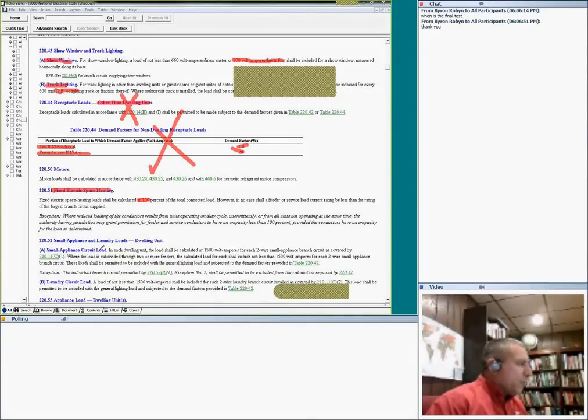And the laundry, small appliances. Can you guys see the small appliance circuit? Dwelling, you need 1500 volt-amps for at least 2 circuits. Laundry circuit, can you see where the laundry circuit is? It says 1. You need only 1 circuit for it, one for each 120-volt circuit as covers this load. So it's 1 circuit here and 1500 volt-amps. Any questions about these? Everybody can see where these are. Any question, my friends?